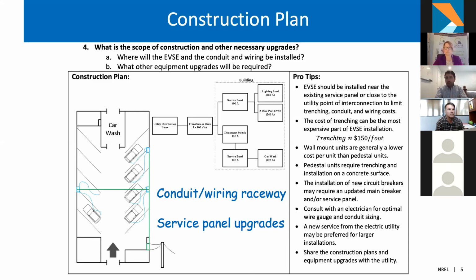So if you have 2 different lights that are each 10 watts, you'd add those together to get 20 watts, then add that on top of the EVSE load, say 7 kilowatts, giving about 7.02 kilowatts as the total coincident demand at any given time. That's really what you need to consider - what is the worst case scenario coming through this service panel if all the devices you want were operating at once.